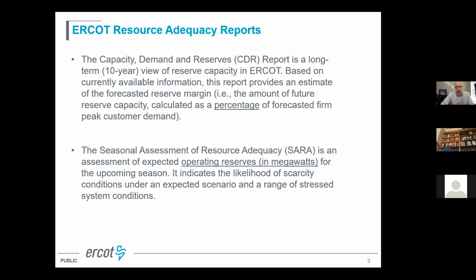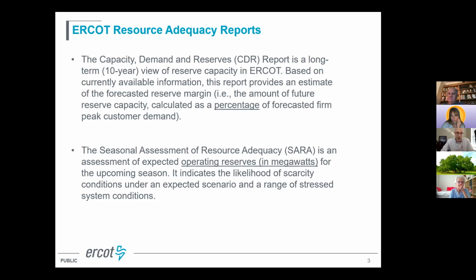Do we expect to have enough operating reserves, or what we call reserve margin, to serve that peak customer demand? The reserve margin is just: you look at your expected peak demand, meaning the amount of power that's going to get used by consumers on the hottest day of summer, then look at the amount of capacity you have above that demand, and express that as a percentage of the actual demand from consumers.